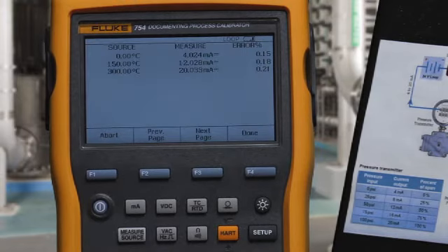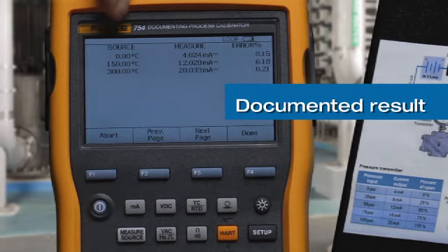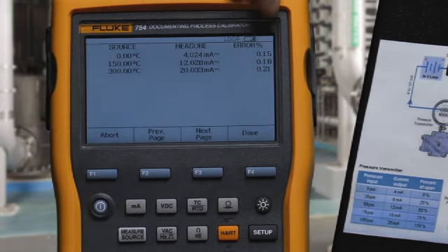When the test is done, you have the documented applied temperature, measured current, and error percent of span for each point.